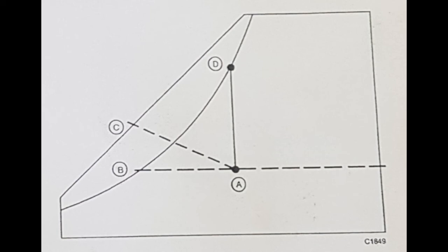Whenever the water temperature is below the dew point temperature, point B, dehumidification occurs as well as dry bulb cooling. This process always falls on a curved line between the initial temperature of the air and the point on the saturation curve representing the water temperature. The exact leaving air temperature depends upon the construction and characteristics of the washer.